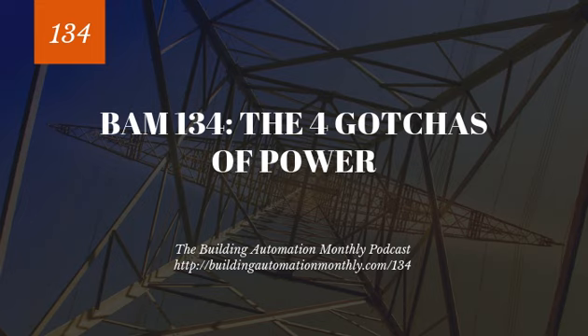So then gotcha number three is basically troubleshooting a rat's nest, as I called it. This is where you start to jump commons, trying to deal with that issue of the shared common by using a bunch of jumper wires. You start using terminal blocks and intermixing AC and DC terminal blocks, and you're like, oh look, there's a ground, I need a ground to terminate to, I'm going to use that ground. Not realizing that that is a DC loop and not an AC loop. And you can create all sorts of issues. Then that creates a rat's nest of issues for you.